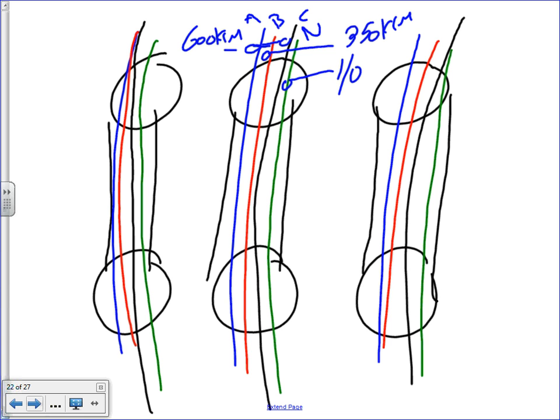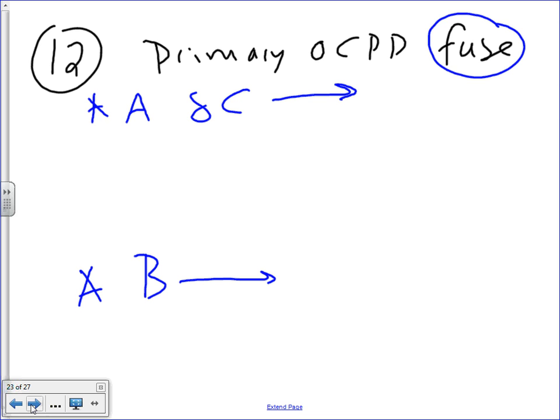Okay, so now you're going to have your neutral running with these conductors, because you have to run a neutral with every load. So that's what the conduits are going to pull. Any comments, guys? Any questions? So that's my neutral. Let's go ahead into the primary fuses. Let's do fuses. Now we're almost done. Hold your horses.